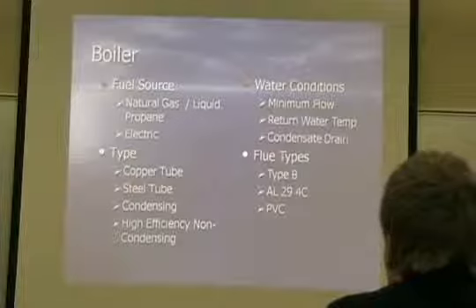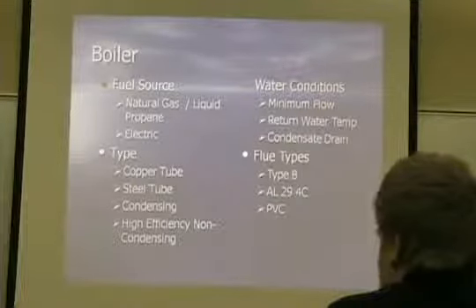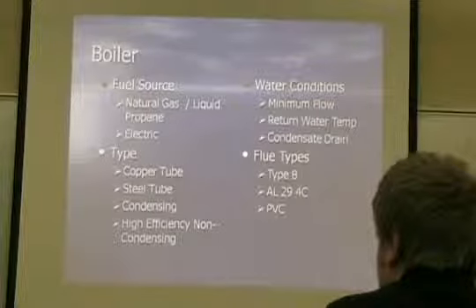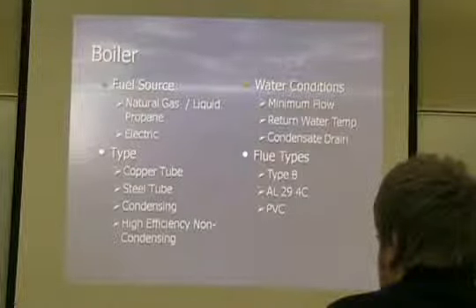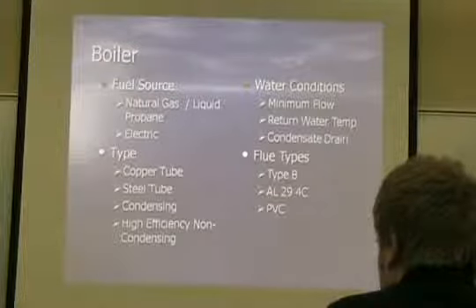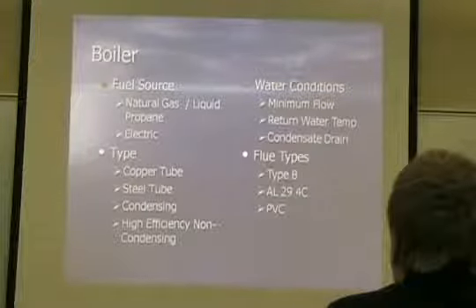Water conditions: there would be a minimum flow. If you had a variable volume application, you want to try to maintain a minimum flow for your pumps, whatever your pumps can turn down to. You're normally controlling your return water temperature to the heat rejection equipment. Condensate drains off the heat pump just like any others. Minimum flow through a boiler, I guess we're talking about boilers. Most boilers are going to have a minimum flow with the exception of that condensing type. So you have to look at how you're piping that up. Return water temperature we talked about; you have to be concerned with it in non-condensing boilers.